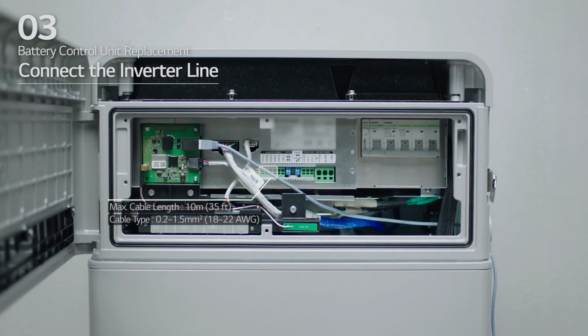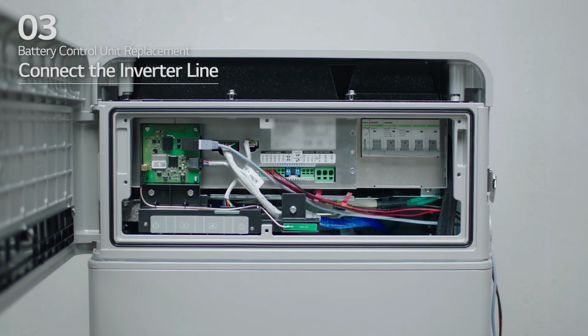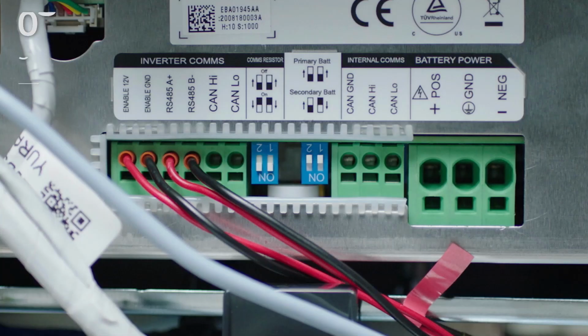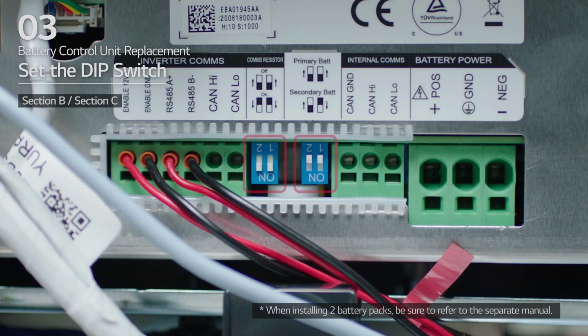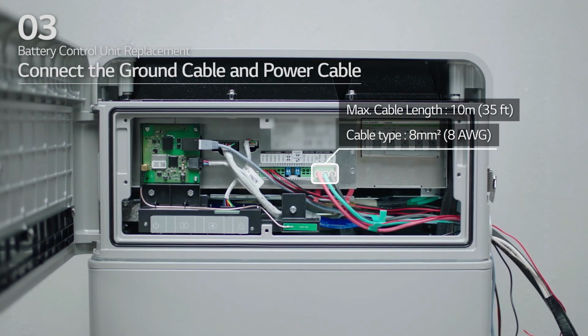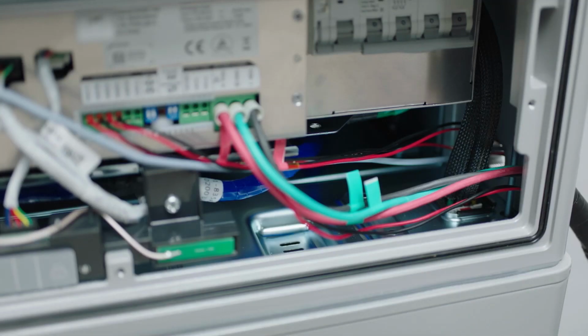Next, connect the inverter line. For the inverter line, select the desired method for communications connectivity. Then, check that the dip switch is set to the default settings. Next, move to Section E. Connect the ground cable and power cable.